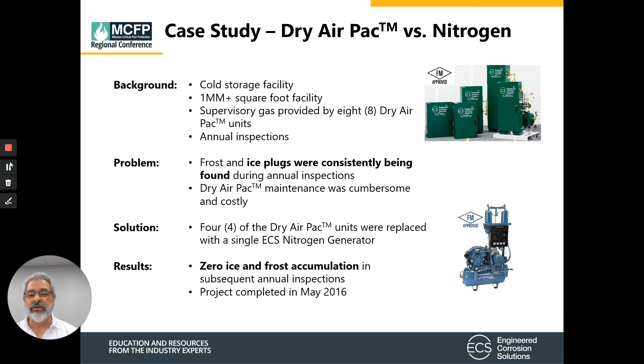Case study two: a cold storage facility over a million square feet where supervisory gas was provided by eight Dry Air Pac units with annual inspections. The problems were frost and ice plugs consistently found during annual inspections, and Dry Air Pac maintenance was cumbersome and costly. As a test to compare the two technologies, four Dry Air Pacs remained and four were removed and replaced with a single nitrogen generator. The results showed no ice or frost accumulation in the systems connected to the nitrogen generator during annual inspections, while the four systems still connected to Dry Air Pacs continued to show frost and ice plugs. This project was completed in May 2016.